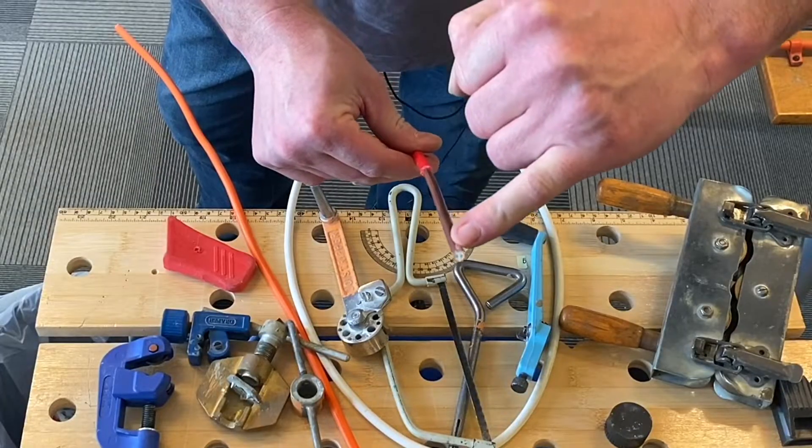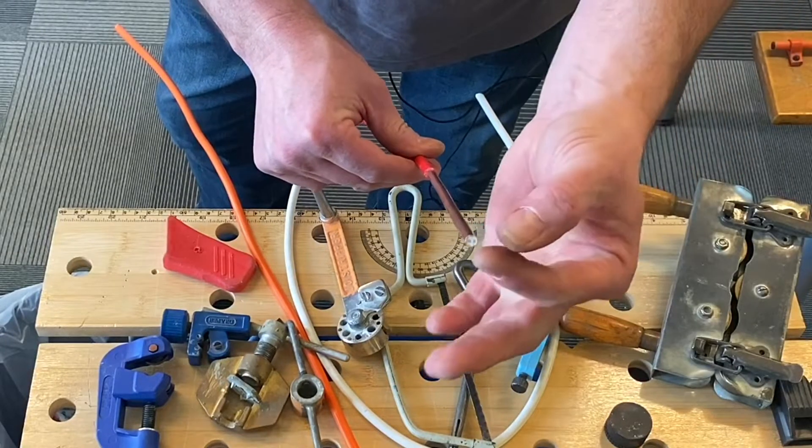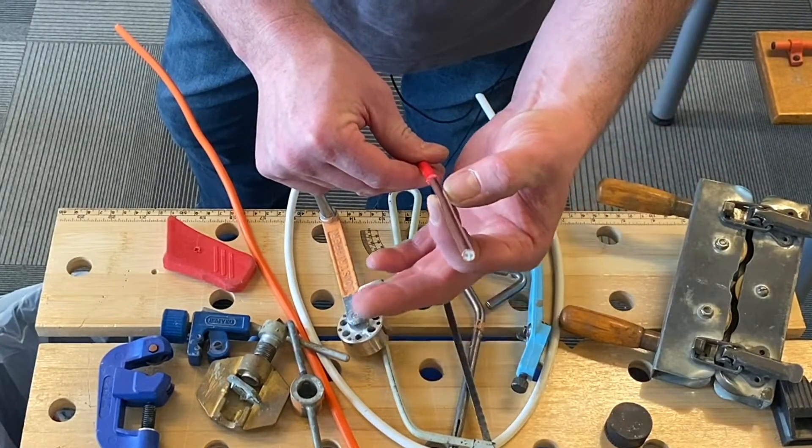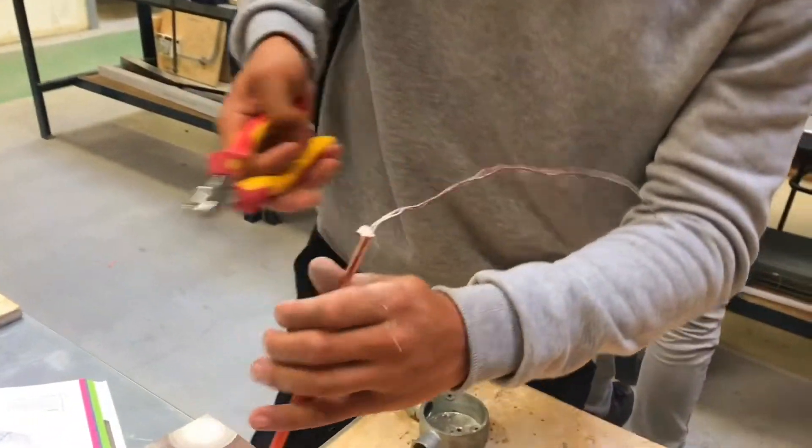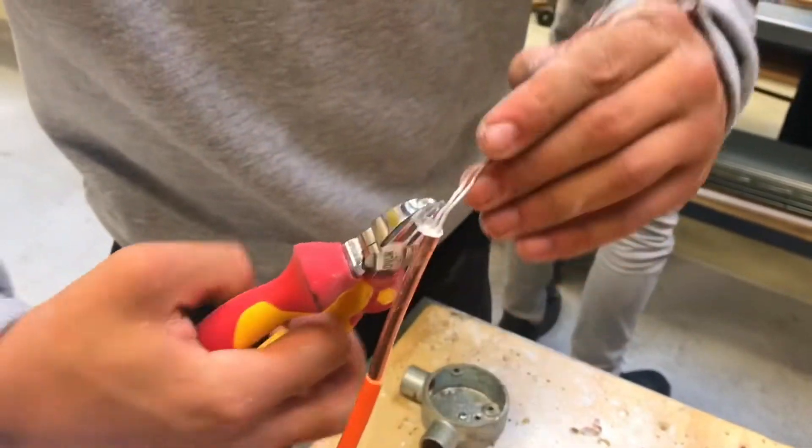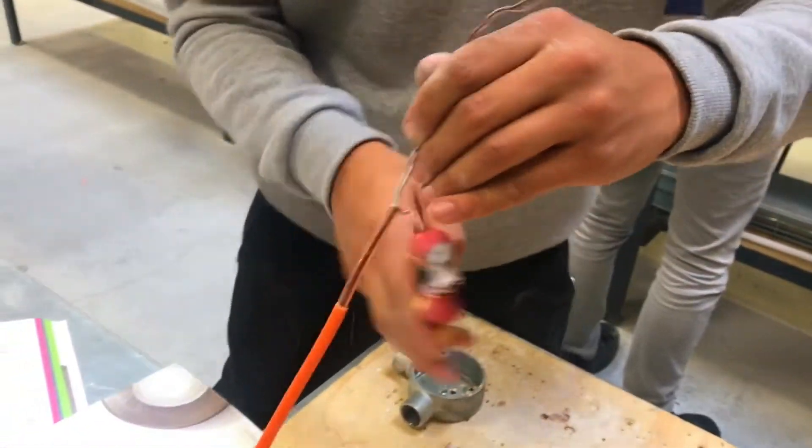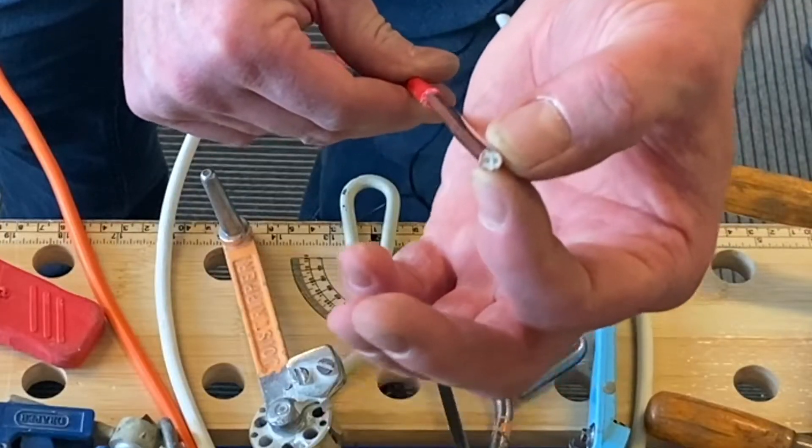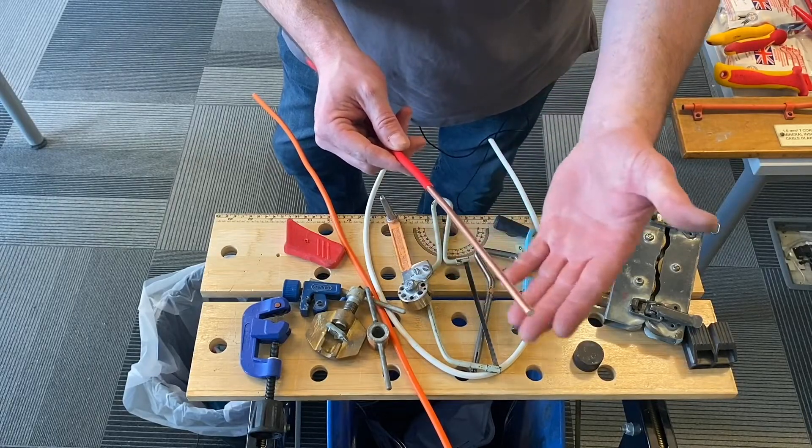It has two conductors in it, so we've got a line and neutral. The outside part here will provide our protective conductor - it's a massive amount of copper, so it makes a fantastic CPC. The construction of the conductors in mineral insulated cable are always solid, never stranded. This is two core 1.5mm.